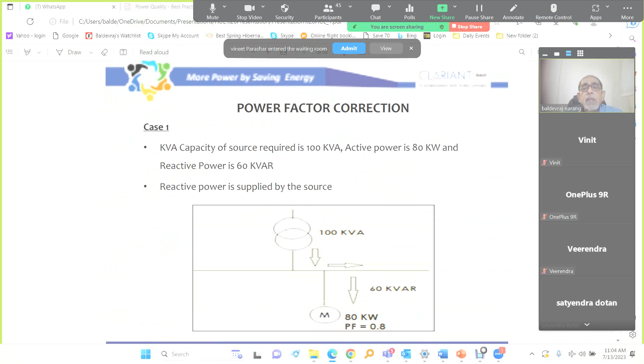Suppose we have a load of 80 kilowatt and we are running it on the grid without any local support of reactive power. So what we need is 80 kilowatt to be imported from the grid and 60 kVAr of reactive power to be imported from the grid, if the power factor of the load is 0.8. So we have two components. One is active power and the other reactive power, and the vector sum is apparent power, which is the billing unit today. So we have to see that we have both economized. The reactive power should be economized to have the optimum billing.